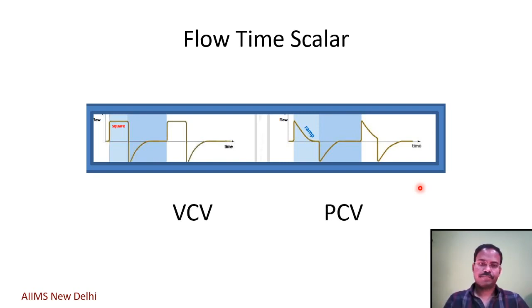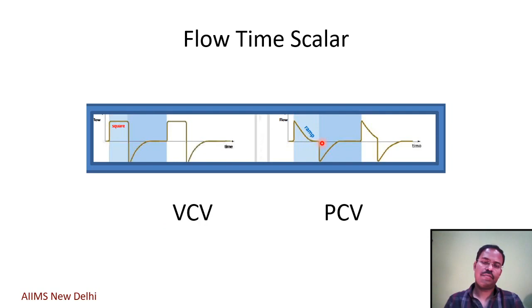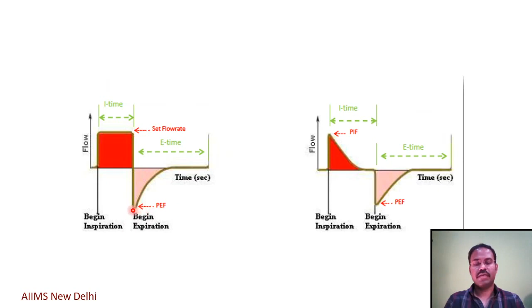Now we'll discuss the flow time scalar. Again, for recap, if you see a square wave flow time scalar, it's VCV mode. If you recognize a descending ramp flow time scalar, it's a PCV mode. Now from the flow time scalar, the basic information which you easily get is the inspiratory time and the expiratory time, and at the same time you can identify and calculate the peak inspiratory flow rate and the peak expiratory flow rate as well.